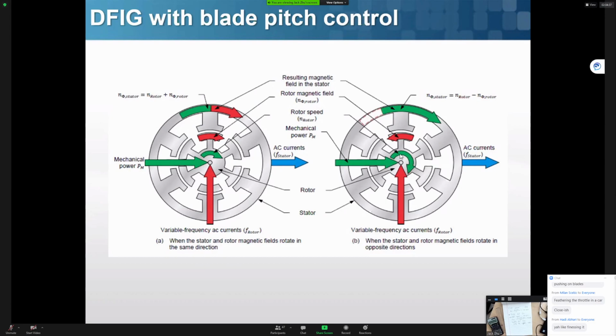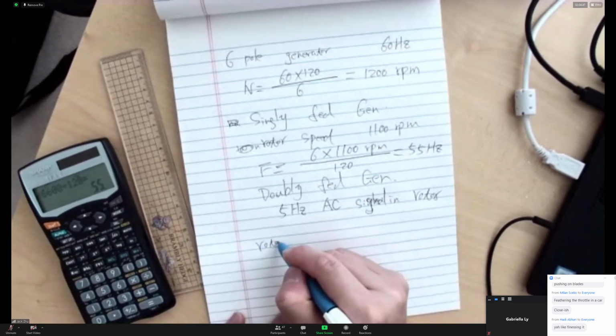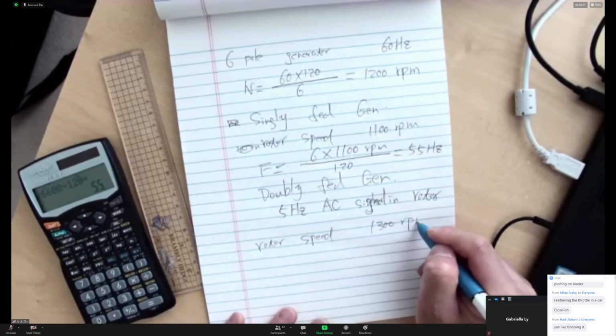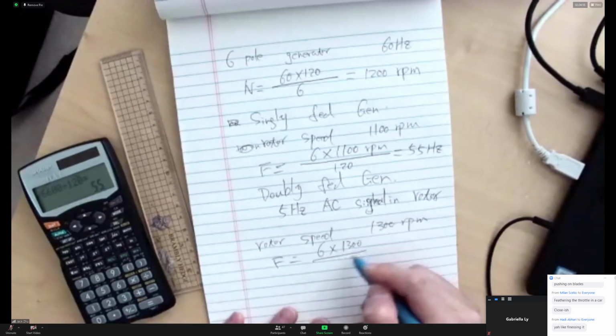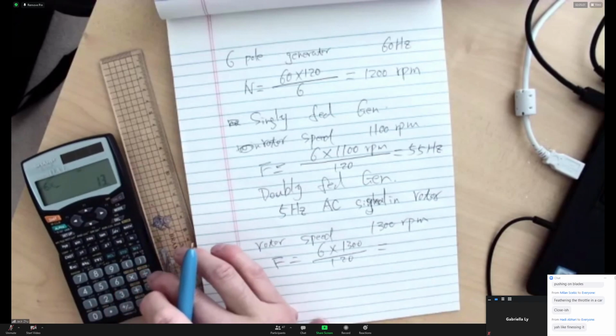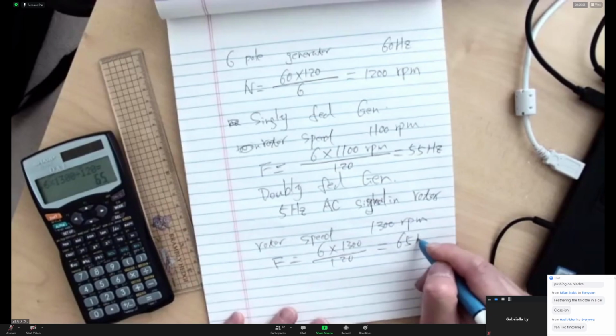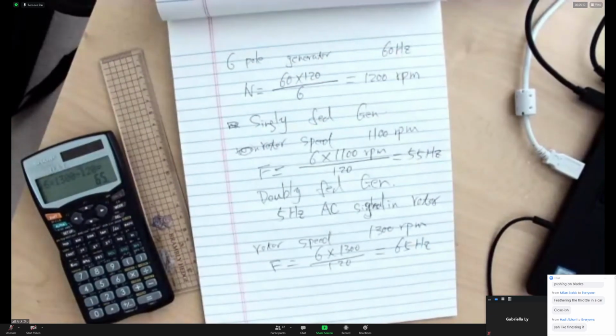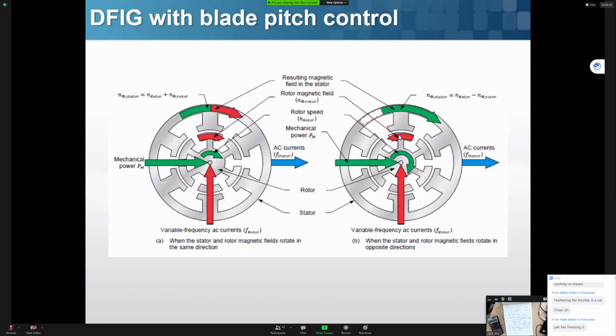What if the mechanical power pushes the rotor to rotate too fast? If the rotor speed is at 1300 RPM, your frequency will be 6 times 1300 divided by 120. You'll get 65 Hertz now, so your speed is faster than normal. What you're going to do is put an AC signal into the rotor, but this time creating a rotating magnetic field in the opposite direction. When you create that opposite direction, you cancel some of that fast running speed, so you still generate that 60 Hertz down here.